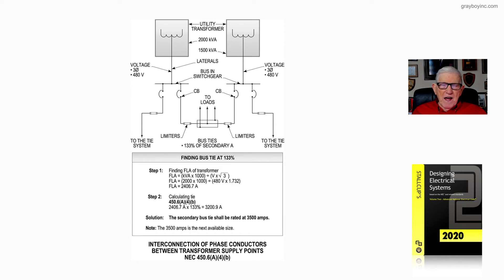So based upon this value in step two, the solution would be that we select the next size bus there. That would be 3,500 amps in rating from the catalog that we selected from. So in the solution then, the next available size above 3,200.9 amps would be 3,500, and that would be the size of the bus TIE that you see from those limiters that you see in the illustration. One and two.